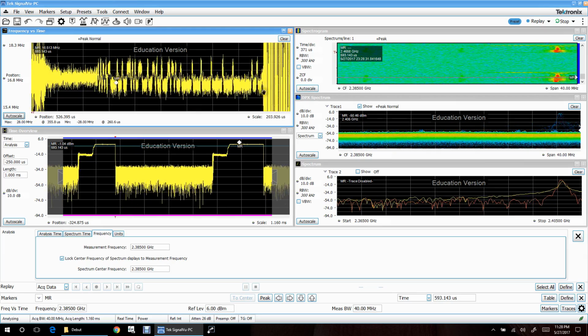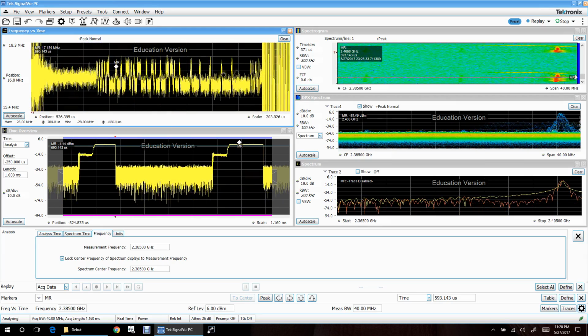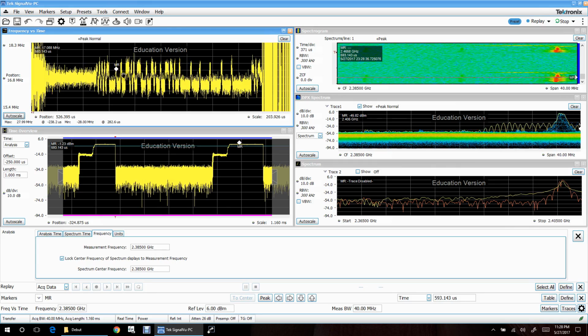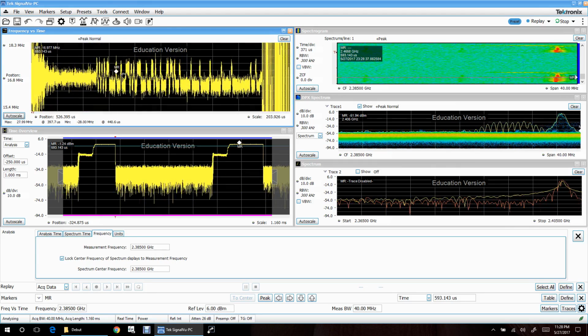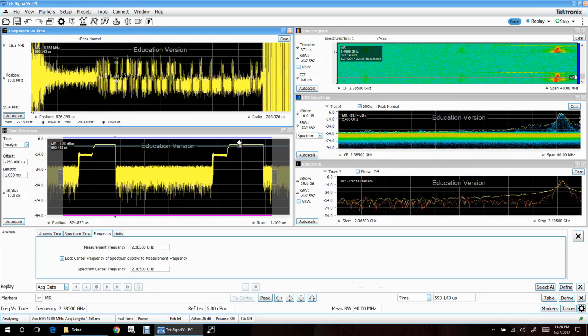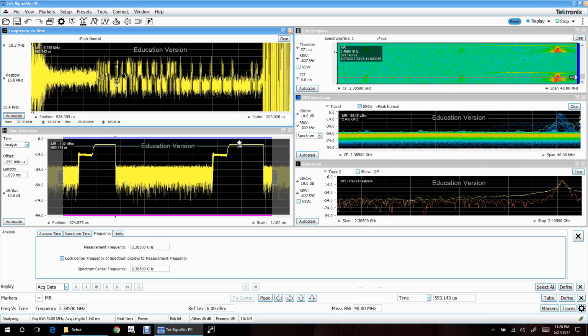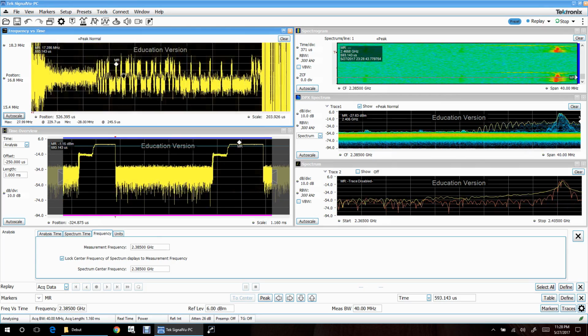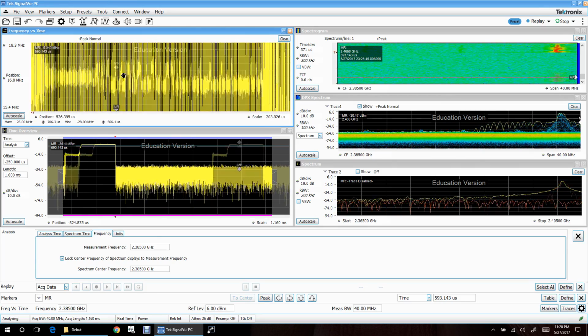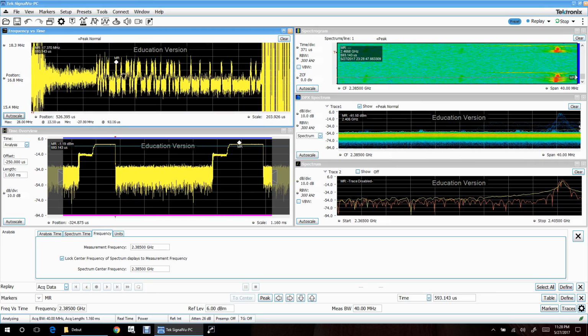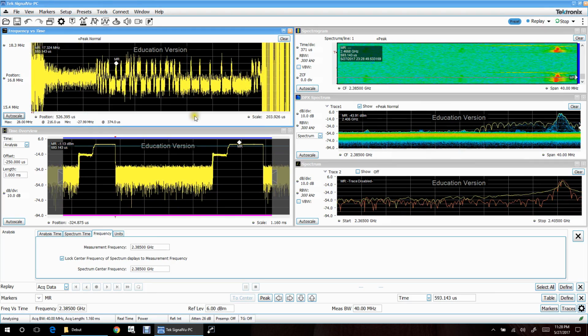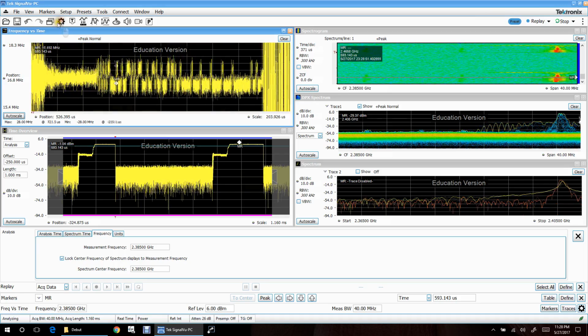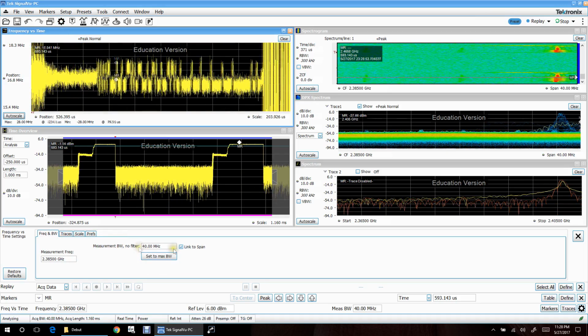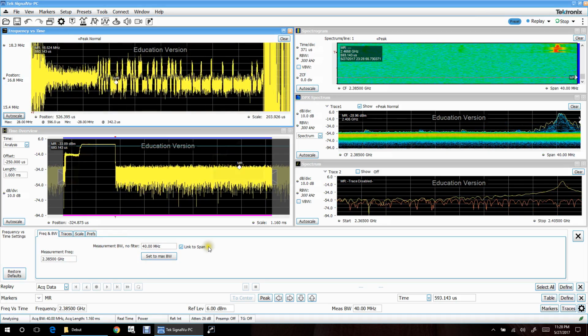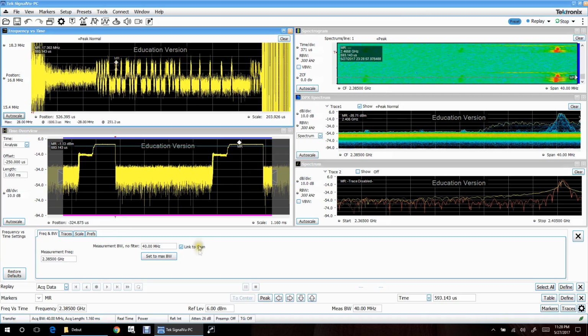Now let's look at this. Now obviously we can see the bits, but it's not very clear, and that's because we're looking at a 40 megahertz bandwidth to do this measurement. And that's not really a good idea, because these are much smaller channels. No reason to try and do FSK computation on an entire 40 megahertz channel. It's going to eat into your dynamic range. And they've thought about this, and you can actually change that setting. So it says link to span. I can remove the measurement bandwidth so that it's not linked to the span.